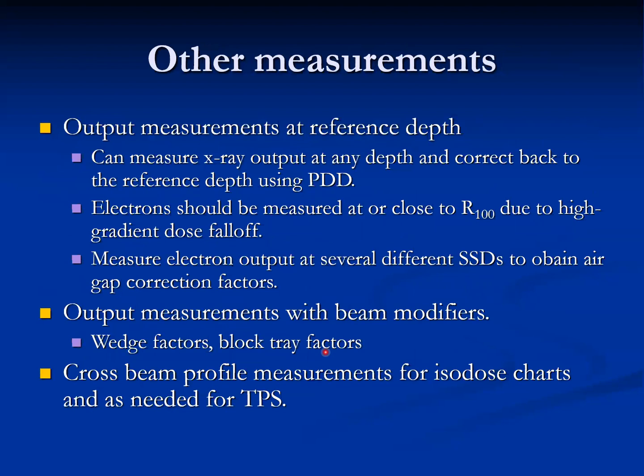Other commissioning measurements include output measurement at reference depth, output measurement with beam modifiers such as wedges, block trays, and MLCs, and cross-beam profile measurements for isodose charts and as needed for the treatment planning system.